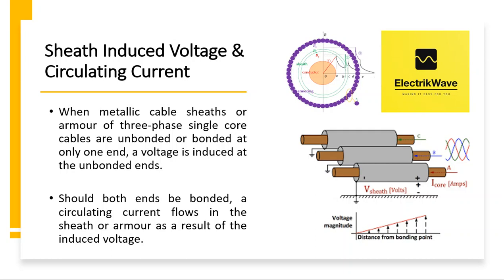When metallic cable sheaths or armor of three-phase single-core cables are unbonded or bonded at only one end, a voltage is induced at the unbonded ends. Should both ends be bonded, a circulating current flows in the sheath or armor as a result of the induced voltage.